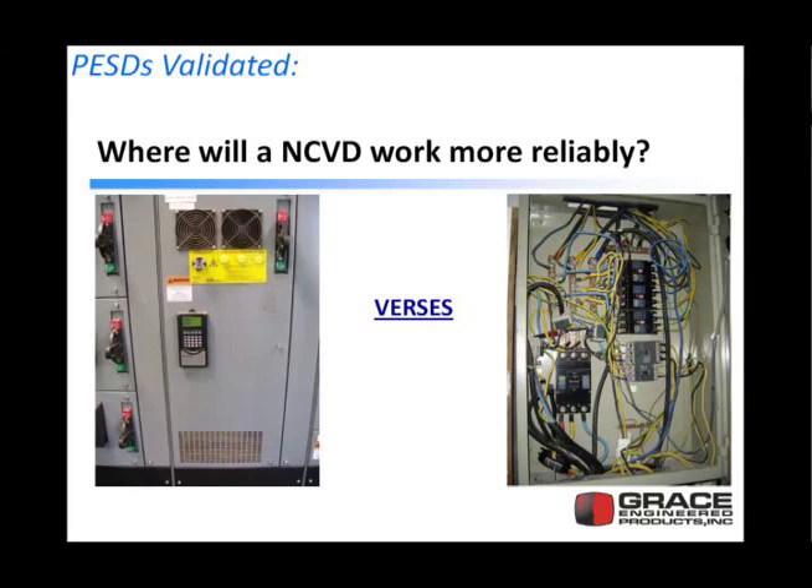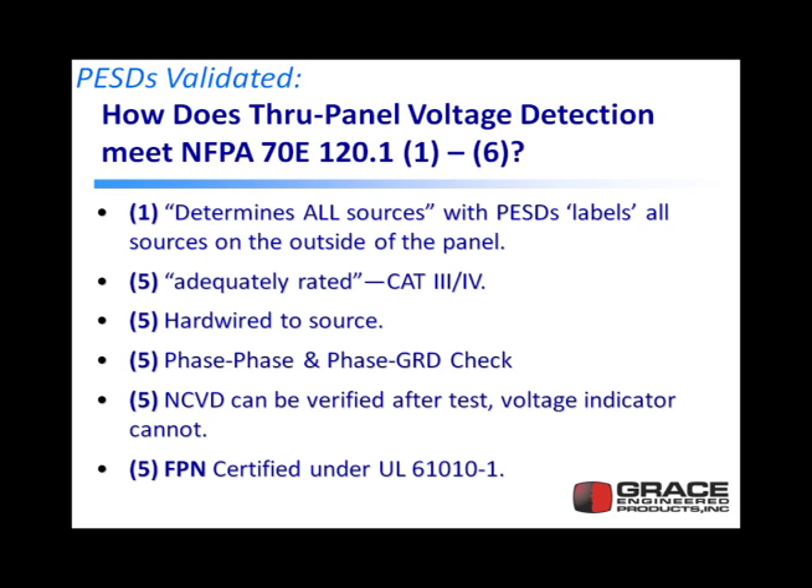By the way we install these, we're reducing the amount of parasitic capacitance within the panel — just by design and installation. Here's a motor control center that's got voltage portals installed. If you put a non-contact pen into a rat's nest of wires, you never know what's going to happen, but we're a lot safer by putting the pen into the motor control center voltage portal.